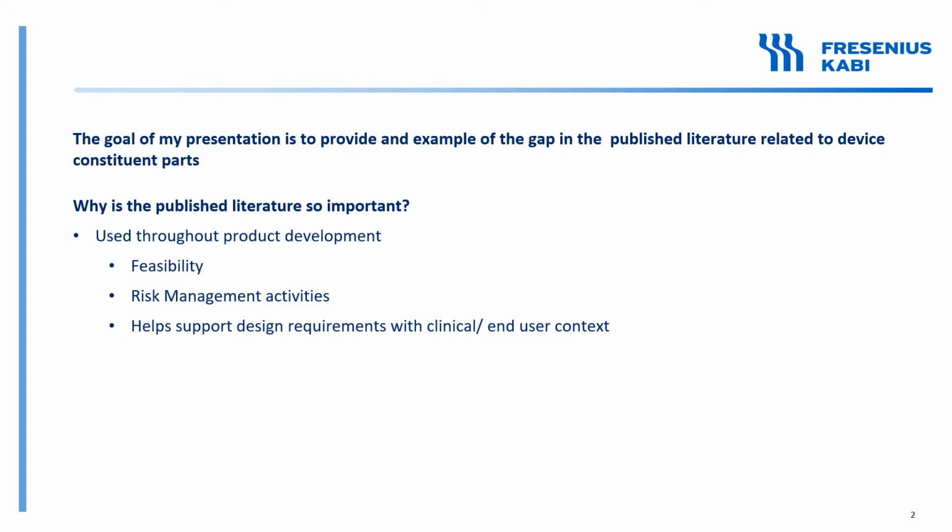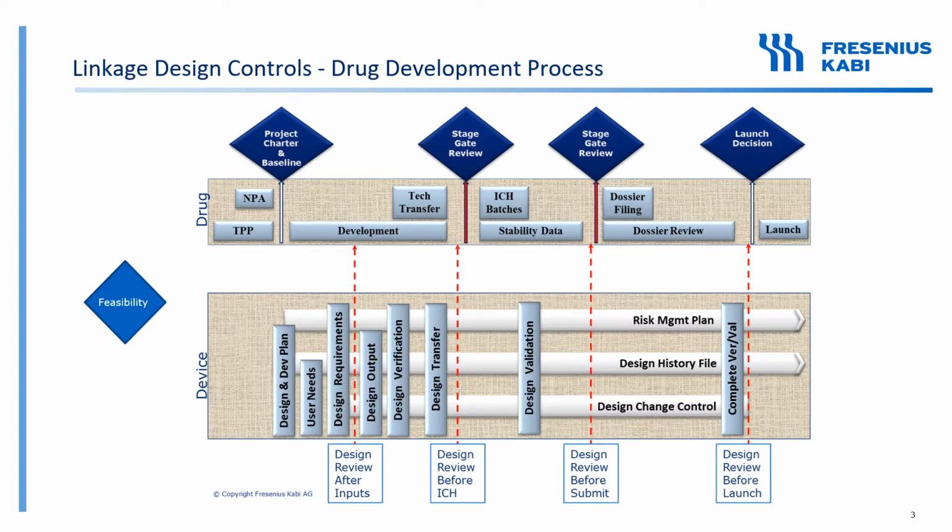We use published data to show predicate devices or similar devices and what use errors they endure, and then how we can mitigate those through our product. And we also use it to help support design requirements with clinical and end user context. Here we demonstrate the linkage between the device design controls and the drug design controls.